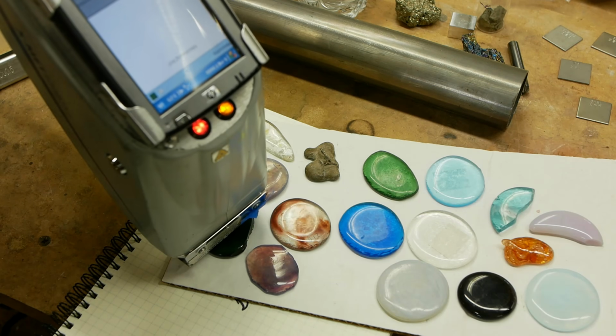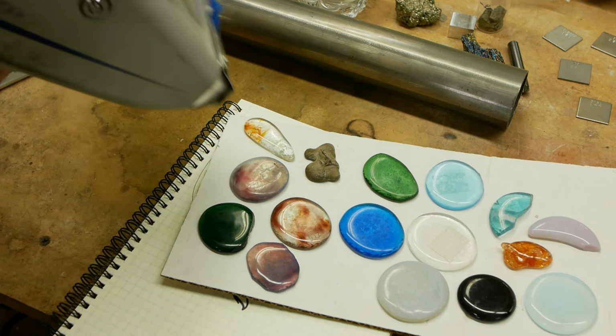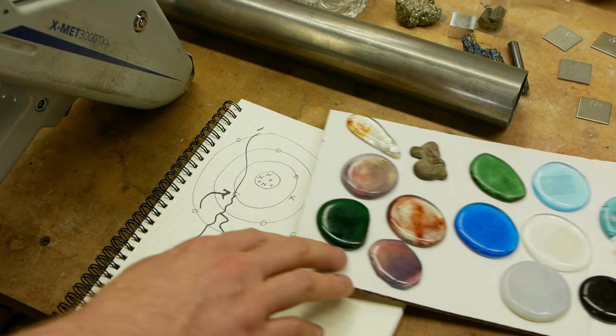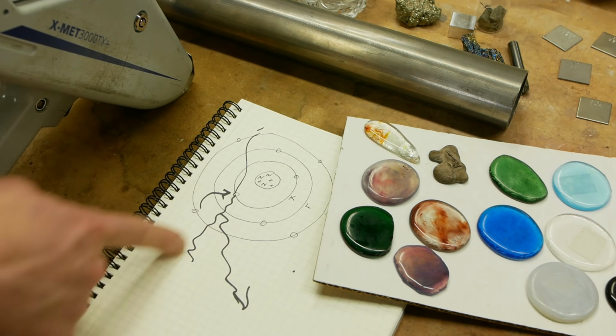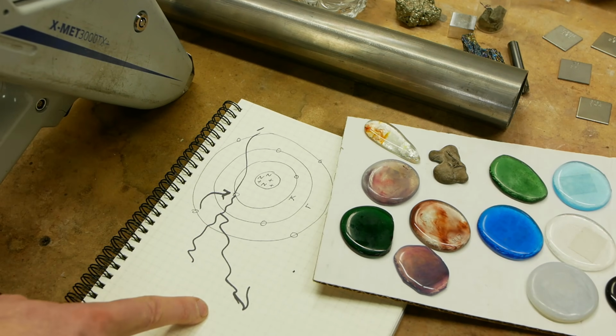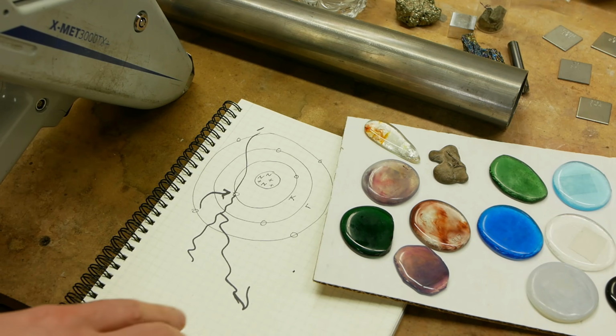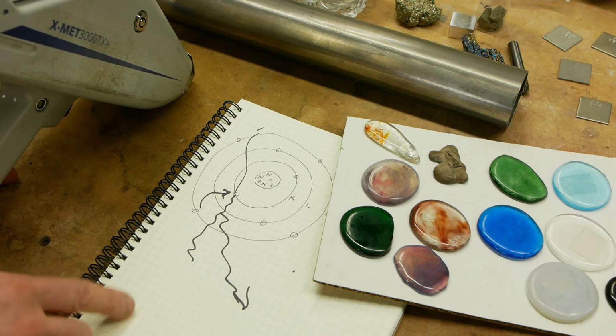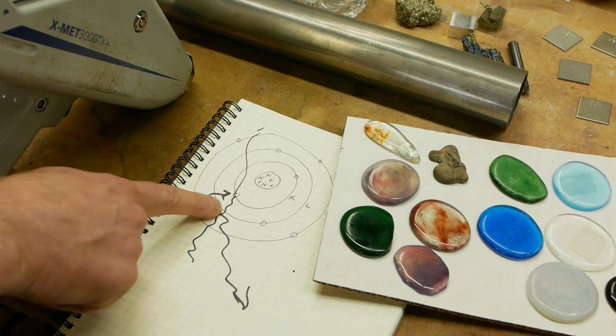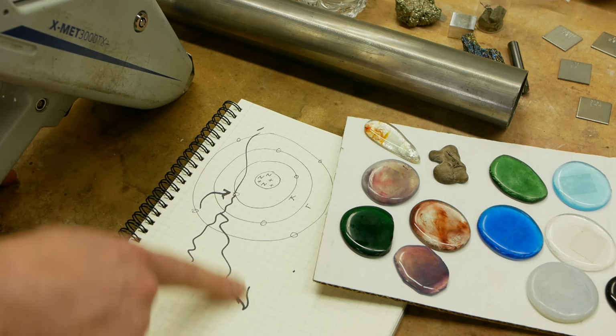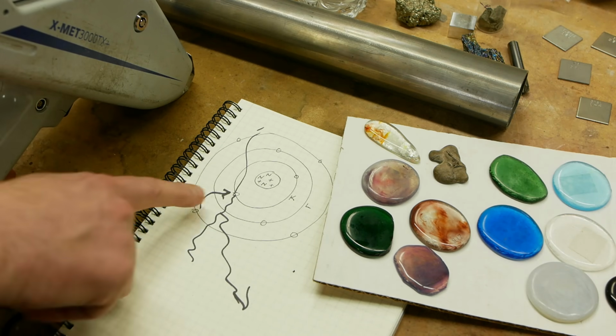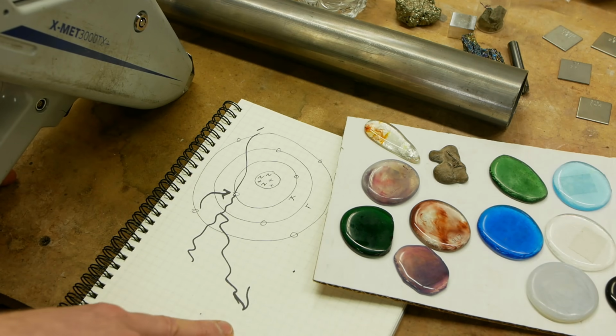The reason that it takes 10 seconds is because it's accumulating all of these return photons. Remember I mentioned that you're putting in a high energy photon, an X-ray photon, and you're getting one back. If you're getting too many back at the same time, we can't easily measure the energy of each one. So instead of just turning up the power on the X-ray tube, which wouldn't necessarily make our job much easier, what we need to do is set the power level low enough that we get back photons that are essentially separated in time, so that we can measure the energy of each one of these photons that's coming back.